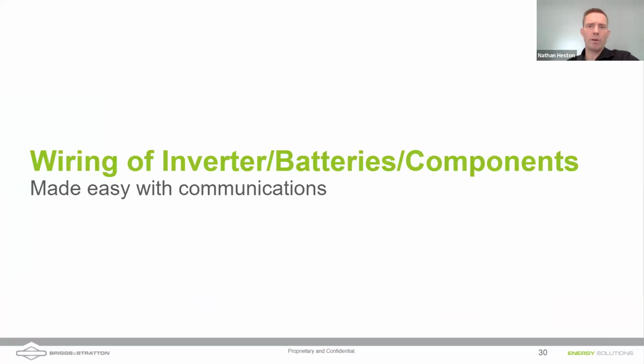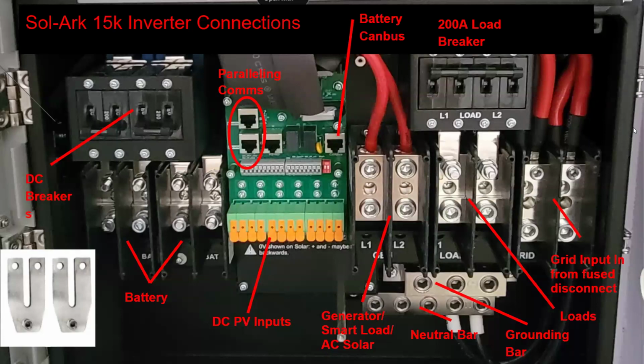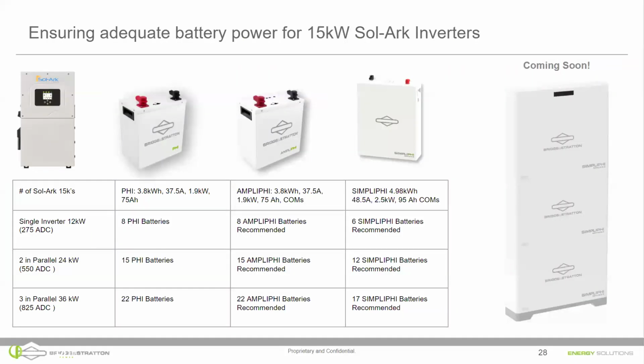Daniel, any more questions that have come in? Yeah, one a little bit related to undersized batteries. Say we did have a Sol-Ark with maybe an undersized battery bank, or maybe an appropriately sized battery bank. What happens if the loads exceed the ability of either the Sol-Ark or the batteries to provide power to the home, with grid up or grid down? A grid down situation, I believe, is what we're asking here.